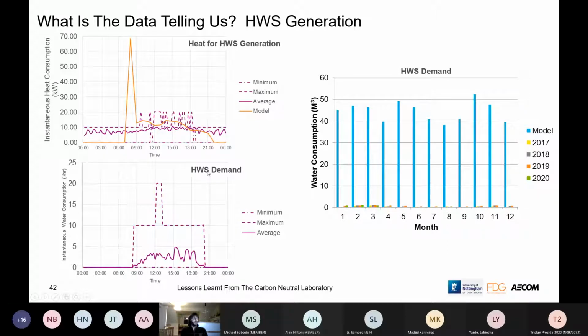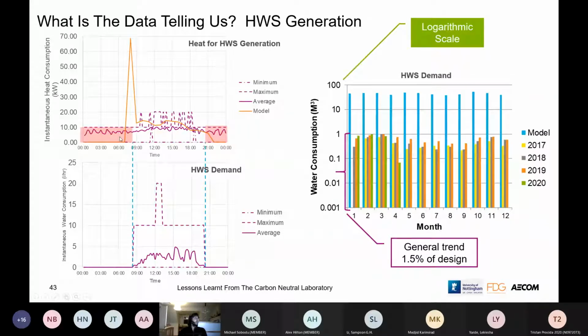In reality, the university have demanded that the hot water system is kept on 24/7. While we can see in the water consumption figures there's no usage at night, this demand graph shows there's still energy consumption, and that's just keeping the hot water pipes hot. So we end up with as much heating demand to keep the pipes hot as we do to actually supply the water for people to draw out of the taps.